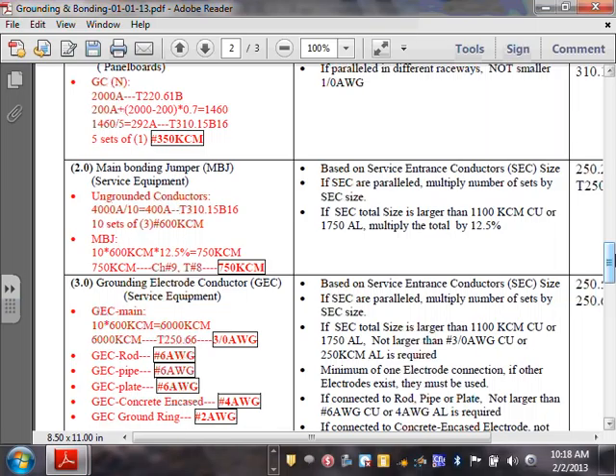She got married and changed her name lately. That's why I always remember how we used to call it 310.16. Now she got married, she changed her name. So 310.15(B)(16). If you go there, under the 75-degree column, you're going to find that you need 10 sets of 3 conductors, 600 kcmil each. Remember, I'm pulling 10. You could have done 11, 500. The nice thing with 10 is it gives you 5 conduits at the top, even, 5 at the bottom. That's better. 11 is an odd number. Might as well go 12 if you want to go there. When you place them, it's not a good idea to have an odd number.